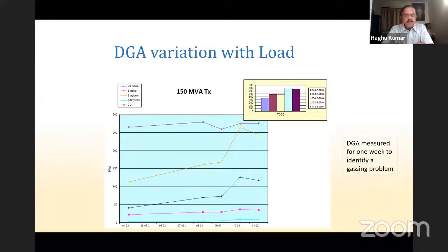In those days, internal inspection meant you had to remove the oil completely. Then one person goes inside the transformer, physically checks, comes out, and finds a solution. In this particular case, it was an eddy current issue in a shield which was loose, which was corrected. Later the gas formation was completely stopped. If the monitoring had not been done, this would have led to tripping and it would have been a major incident.